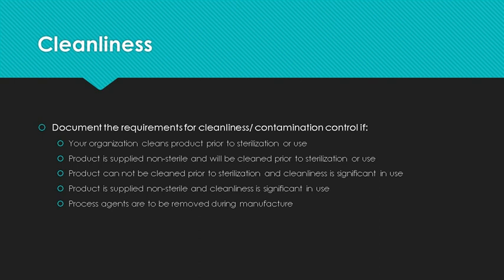Going into production, your organization must determine if it is responsible to keep cleanliness or contamination records. You must keep records if you clean the product prior to sterilization or use; or you send the product non-sterile and the customer cleans it prior to sterilization; or product can't be cleaned but cleanliness is significant in use; or product is supplied non-sterile but cleanliness is significant in use; or processing agents are to be removed during manufacture — think mold release agents.